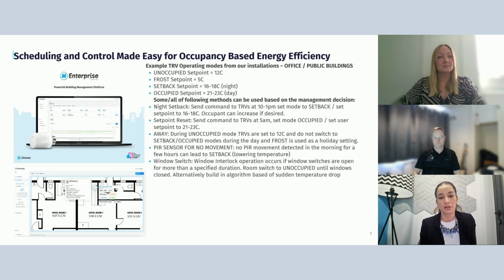You can have a frost setpoint of 5 degrees. And then you can have a setback point, which can be either at night if it's a residential or a retirement home. It can also be a setback point for after hours, for example, for working offices, schools and universities. Again, in most cases, it's 16 to 18 degrees at night. That alone is a big saving in itself, just reducing the temperature at night by a few degrees. I think 1 degree usually translates into 5 to 7% savings on the energy side.